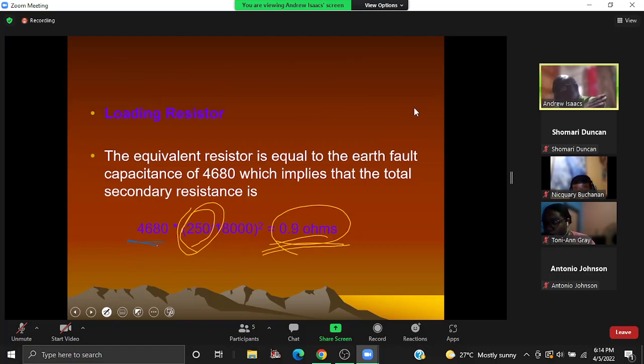So you connect that small resistor, that 0.9 ohm resistor. It's reflected in the primary. So you now end up with a large earthing resistance, which then limits the current in the neutral for your generator, reduces the fault current, but then produces a large current in the secondary, or to the relay, that you can use for relay operation. So you have the 0.9 ohms.